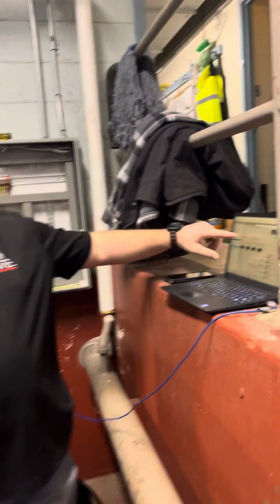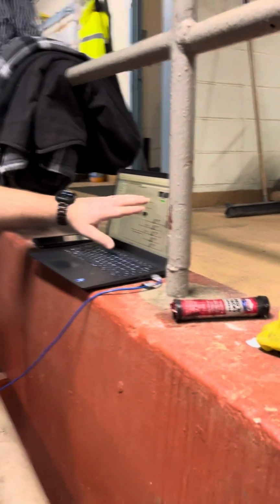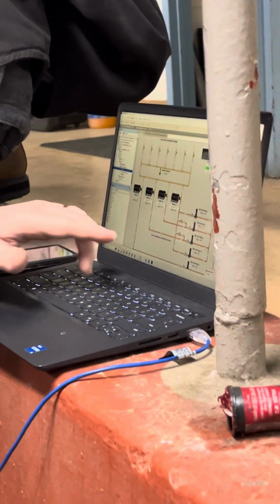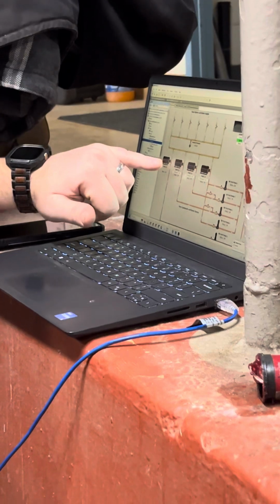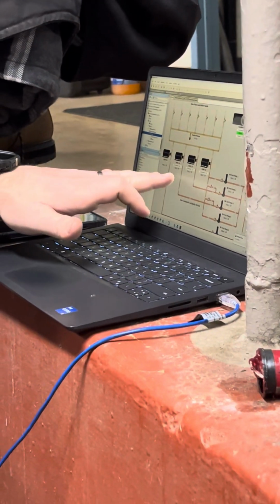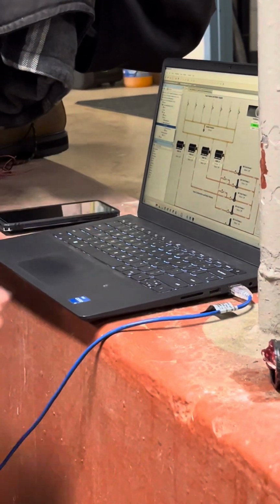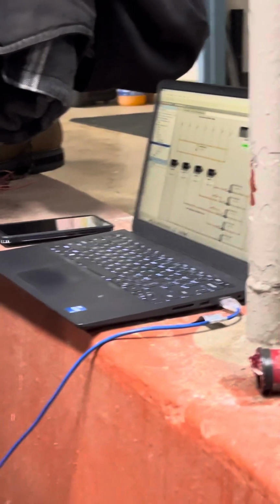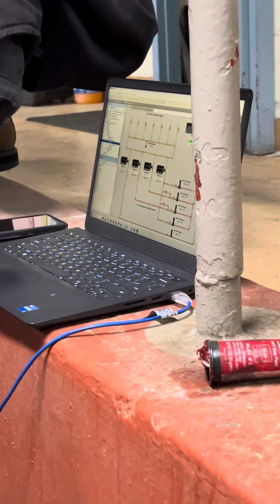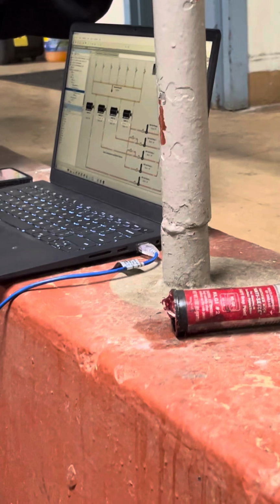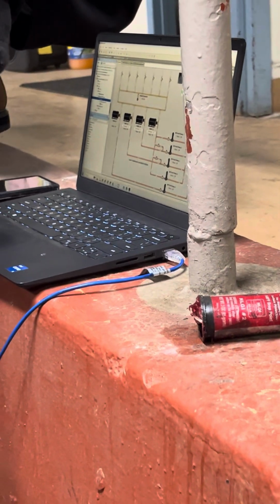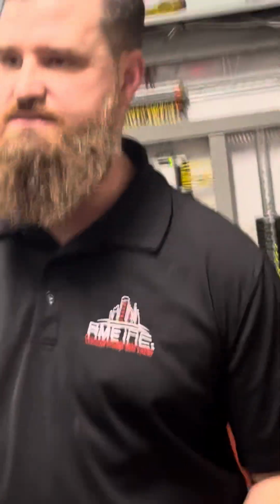So, going out to the field, we have the zone valves. I have no control of that. That is through the other BMS system. You have boiler 2, which is the big guy behind you. It's listed as boiler 1A, 1B, and 1C. Just equate that to 1, 2, and 3, okay? All right. Now, 1, 2, and 3, we have the ability to operate and control. Boiler 2, we only get status, okay?